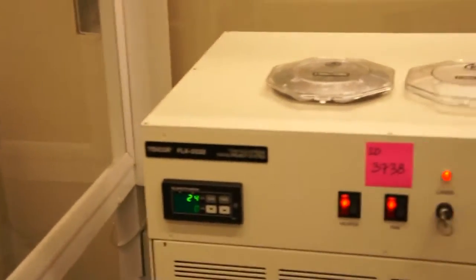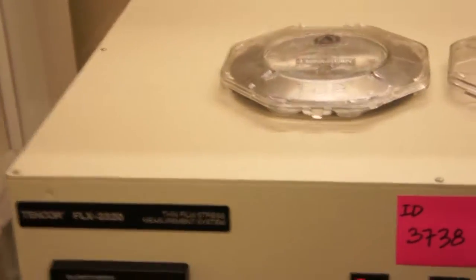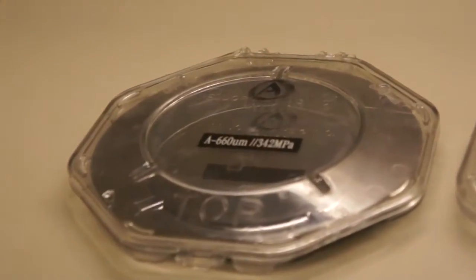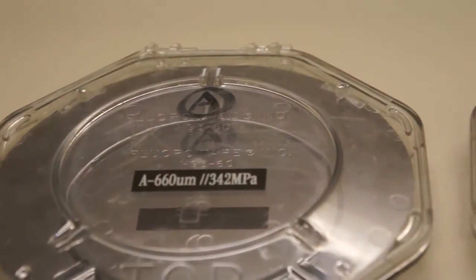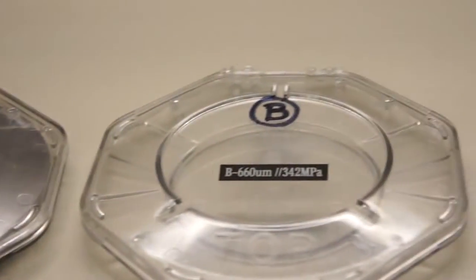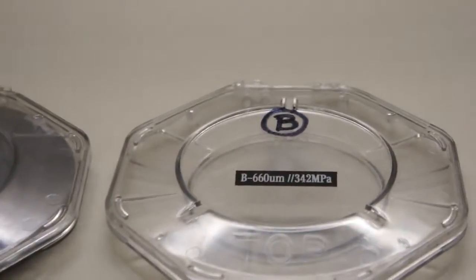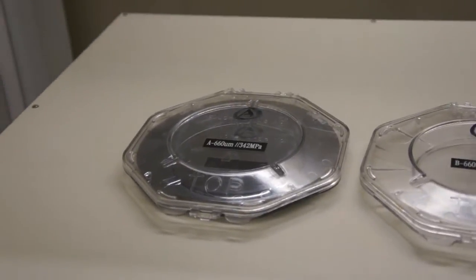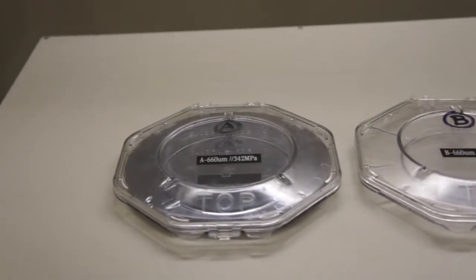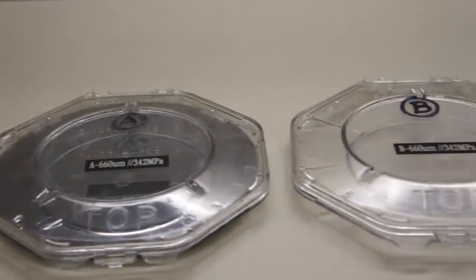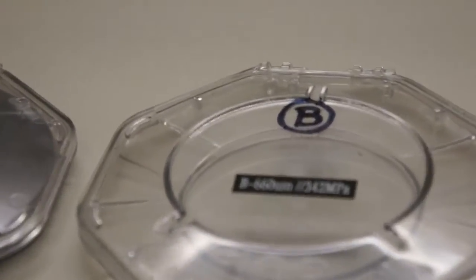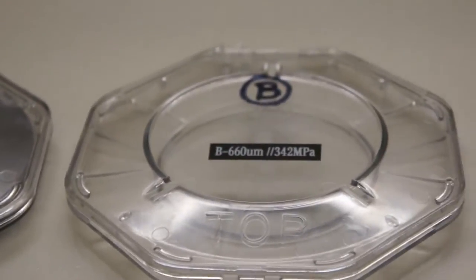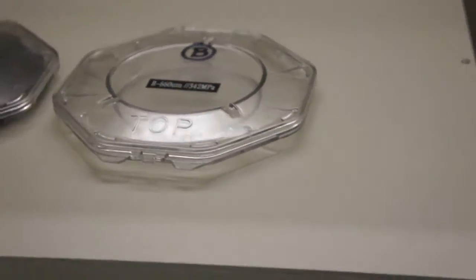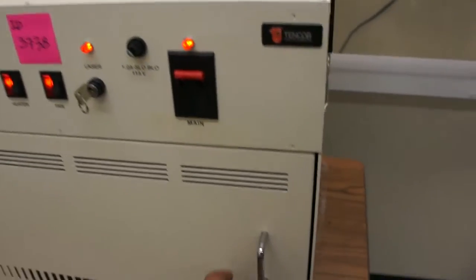Okay, I already pre-measured our first measurement on wafer A, and these wafers measure 342 megapascal for the demo. The proof of life video. I went ahead and started by measuring wafer A. So we're going to be in the process of measuring wafer B and to get to our measurement of about 342 plus minus 5%.